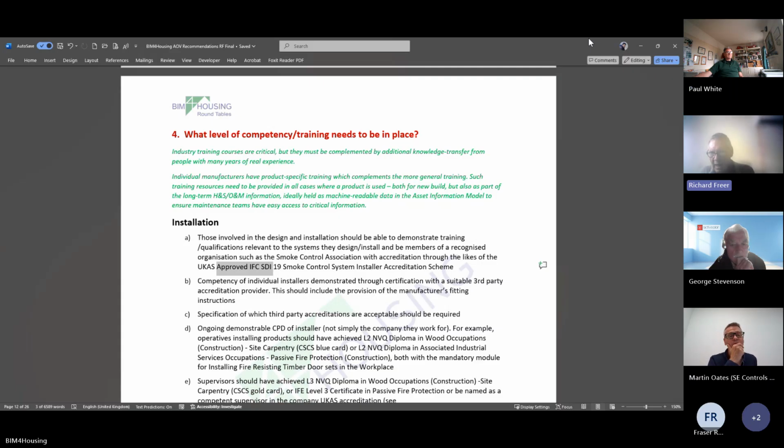So basically now, as right this moment, it's all SDI. It's SDI 19. It's all wrapped up in there. There's nothing else we need to include. Yeah, but SDI 19, and they will tell you themselves, they do not assess individuals' competencies. They assess the competency of the organisation. Right. Yeah, we've had this before, haven't we? They'd check the certification there, Richard. They'd look for the EN 12101 Part 2 certification of the NSHEV, and that would tick the box.